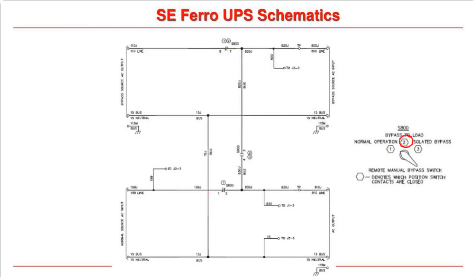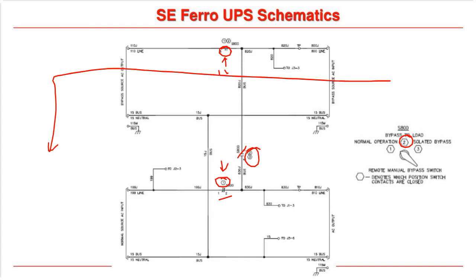Now, when we go to position 2, you can see up here that this has a position 1 and a position 2. So this remains closed, okay? But this one here doesn't have a number 2 next to it, so this opens. But it is a make before break switch, and this has a number 2 on it as well, so this actually closes before this one opens. What you're supposed to do is, your bypass is going to be coming out to your static switch in here. So your static switch, okay? And it's normally choosing the inverter output.